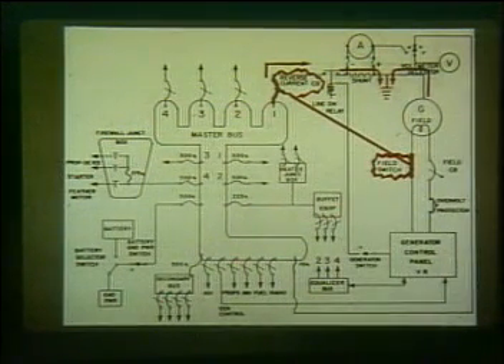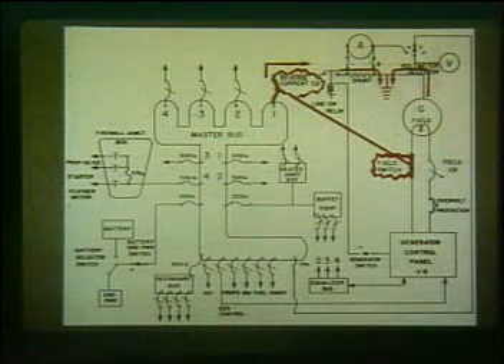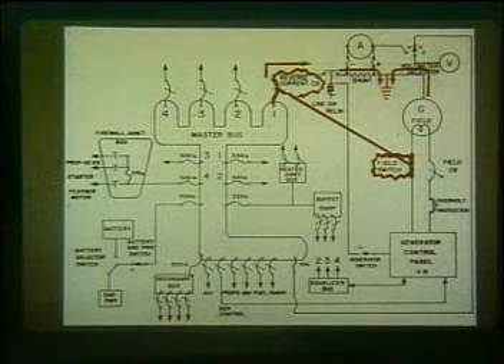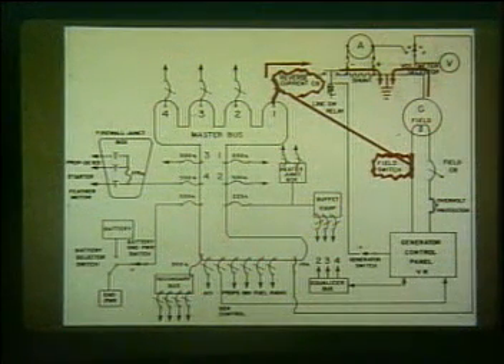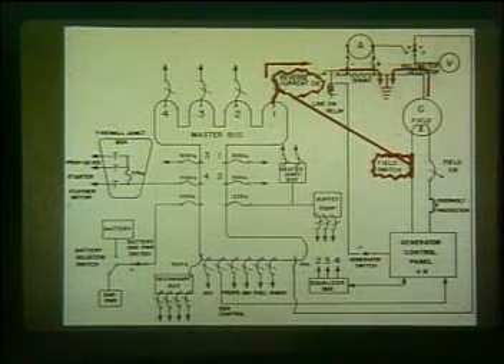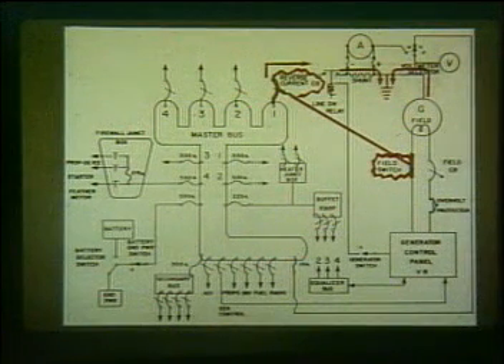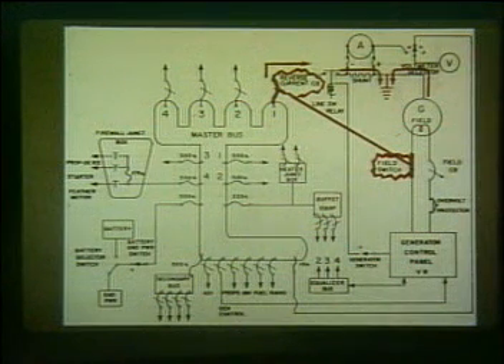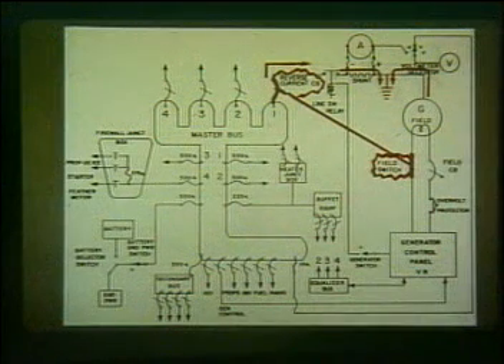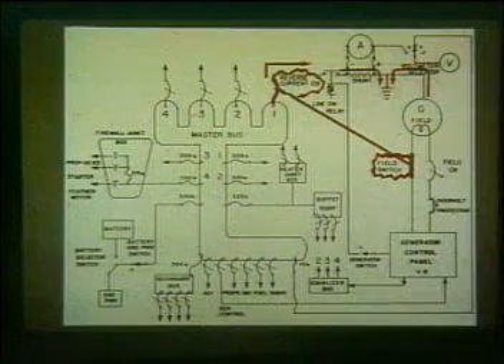The reverse current circuit breaker is provided to protect the master bus in the event of a short in the generator output feeder cable. When a reverse current of 300 amps from the master bus toward the generator occurs, the reverse current circuit breaker will open, isolating the master bus. At the same time, it will break the generator field circuit by opening the field switch. This field switch is an integral part of the reverse current circuit breaker and opens any time the reverse current circuit breaker is tripped.